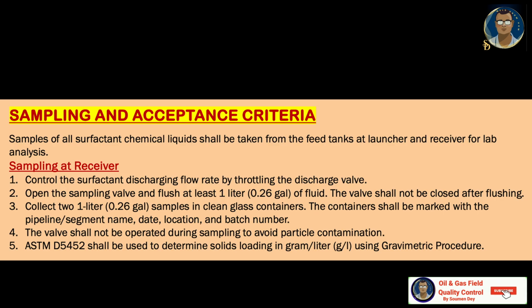Collect two 1 liter or 0.26 gallon samples in clean glass containers. The containers shall be marked with the pipeline or segment name, date, location and batch number. The valve shall not be opened during sampling to avoid particle contamination. ASTM D5452 shall be used to determine the solids loading in grams per liter using the gravimetric procedure. The acceptance standard should be less than 5 grams per liter.